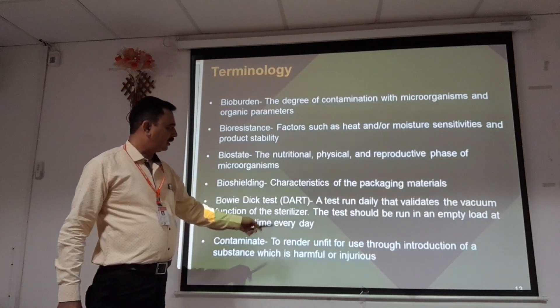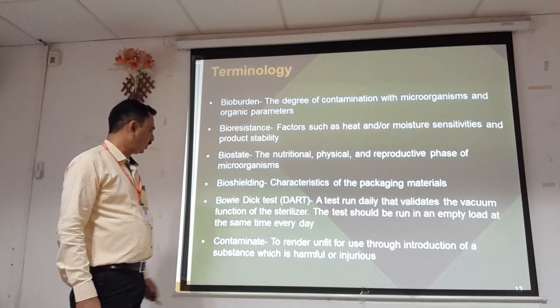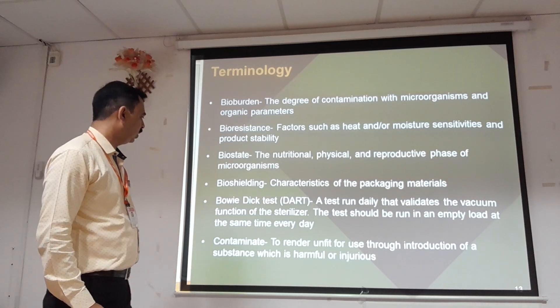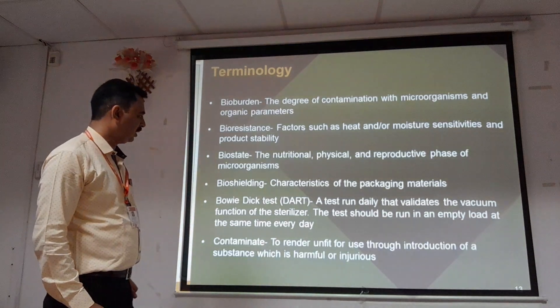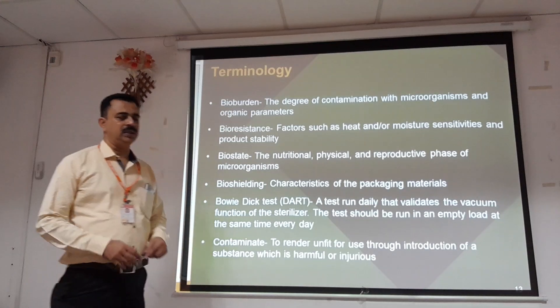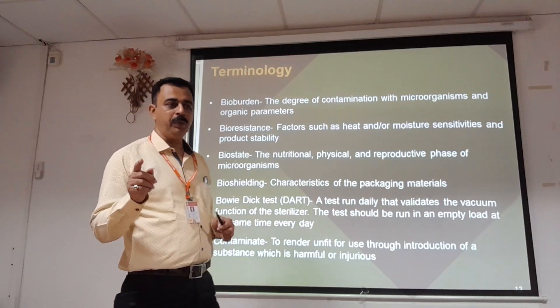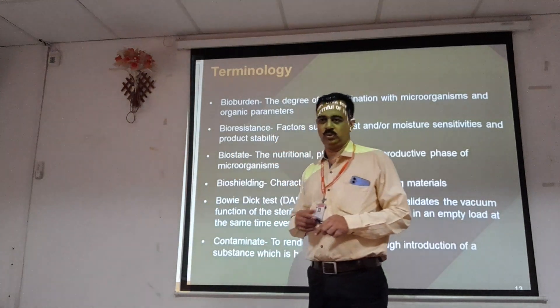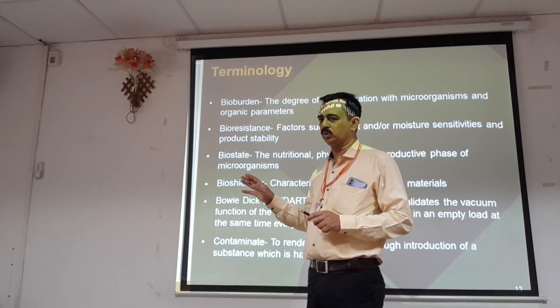The Bowie-Dick test is the test that runs daily to validate the vacuum function of a sterilizer. The test should be run in an empty load at the same time every day. This relates to the autoclave method of sterilization, and materials must be properly processed through the autoclave.